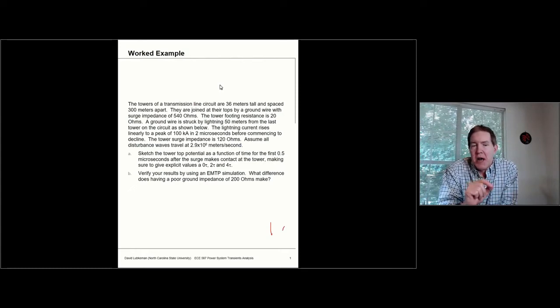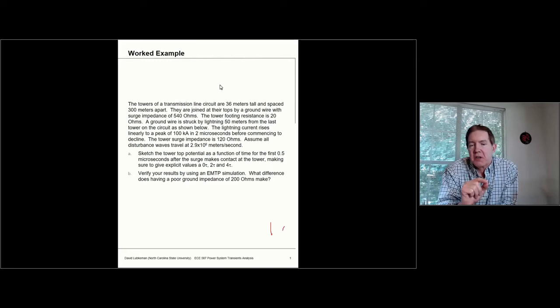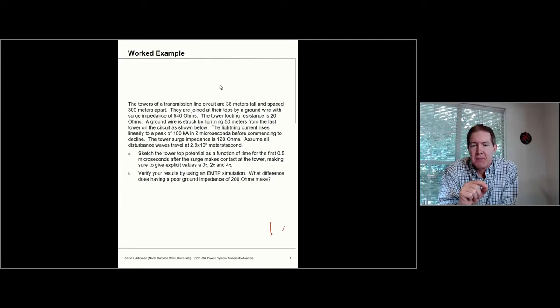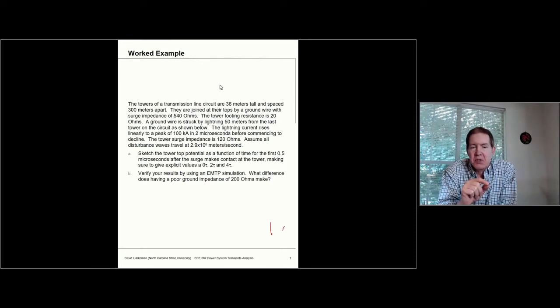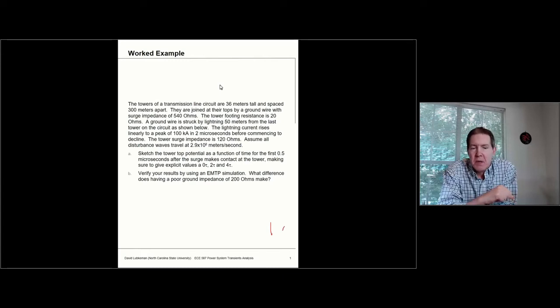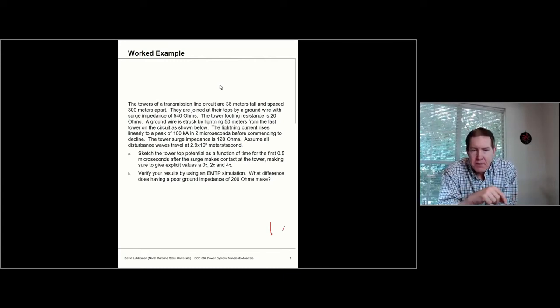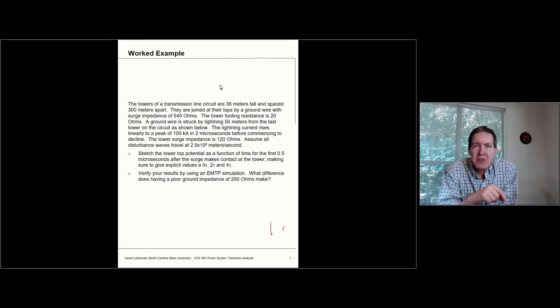We're going to assume that the ground wire is actually struck by lightning first, and it's going to get struck 50 meters from the last tower on the circuit. This is going to be a massive lightning strike — we'll assume a peak 100 kiloamps reached in 2 microseconds, after which it tails off. The tower surge impedance is 120 ohms, which is a typical value, a little bit over 100 ohms for a tower.